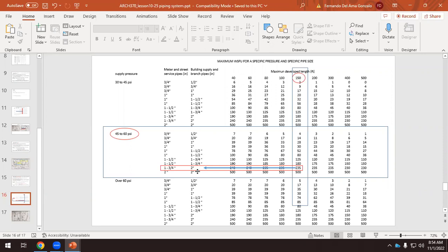And then one here in this restroom. I think that was well, there was another branch here, but this is the when we are out of the toilet. This is what we have. The minimum from the city supply. The first pipe, the minimum should be 2 inches.